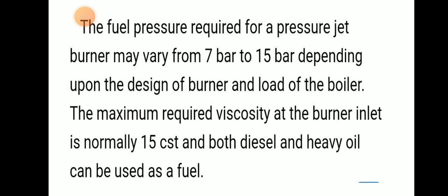The fuel pressure required for a pressure jet burner may vary from 7 bar to 15 bar depending upon the design of the burner and the load of the boiler.